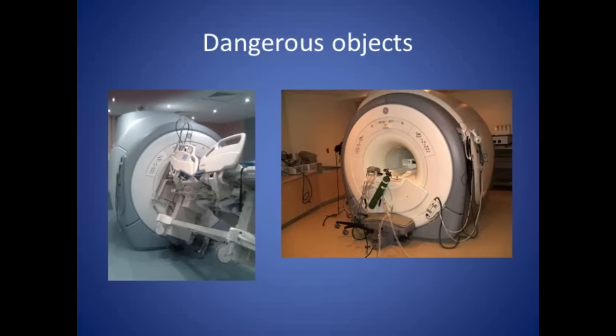Here are two examples of ferromagnetic objects that were brought into the MRI scan room. The patient bed, seen on the left, weighs approximately 500 pounds and is pulled completely off the ground. The steel oxygen tank, which weighs about 10 pounds, is pulled with a force of 1,500 times its weight. That's 15,000 pounds of force, much like getting hit by a 2,000-pound car at 30 miles an hour.